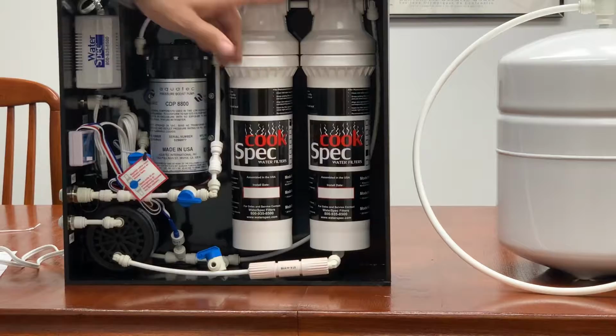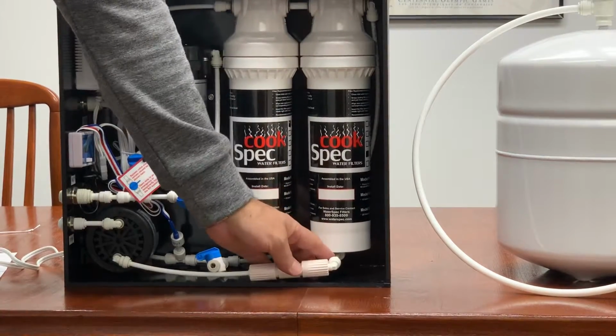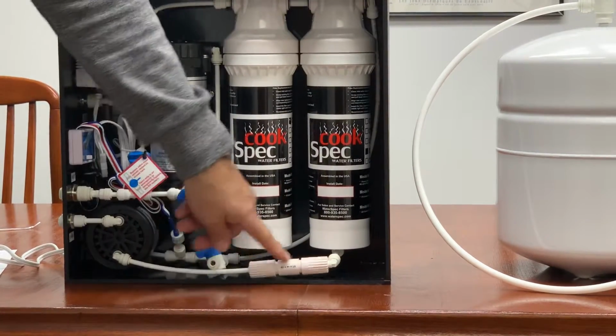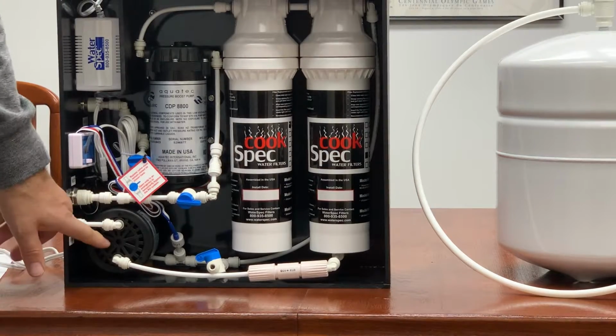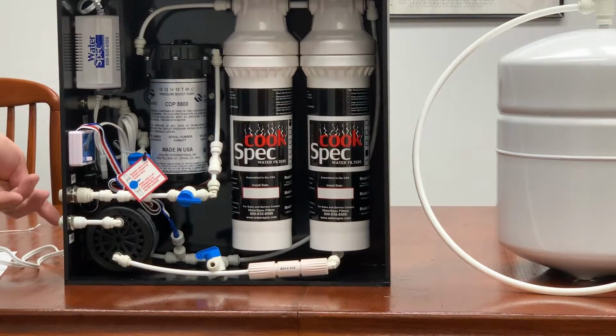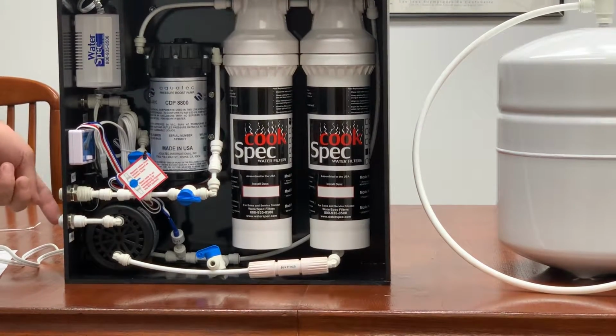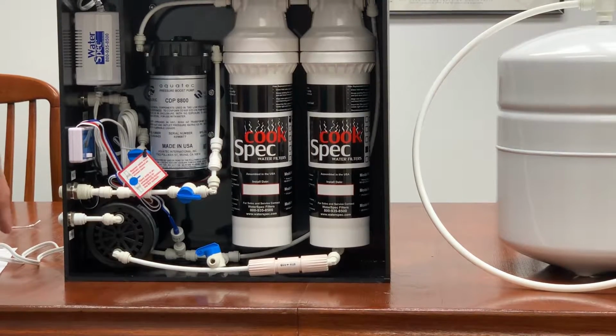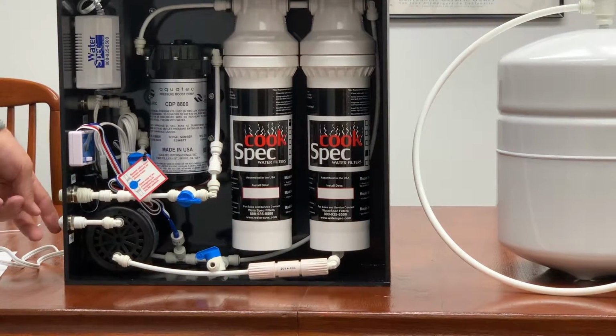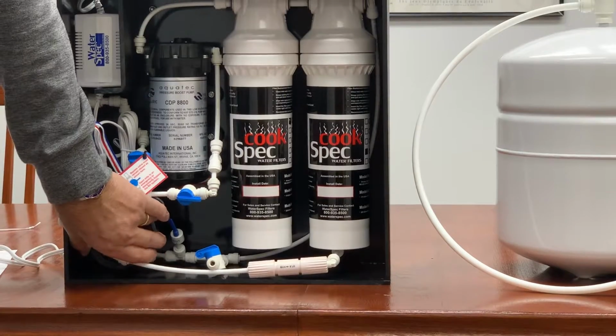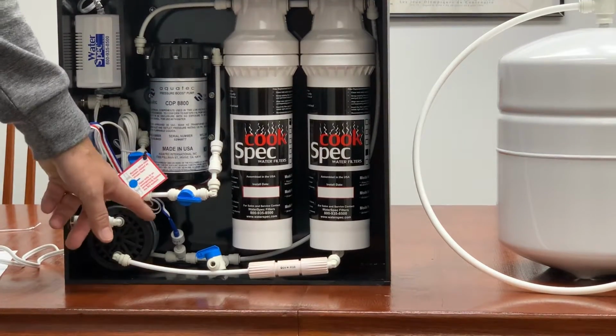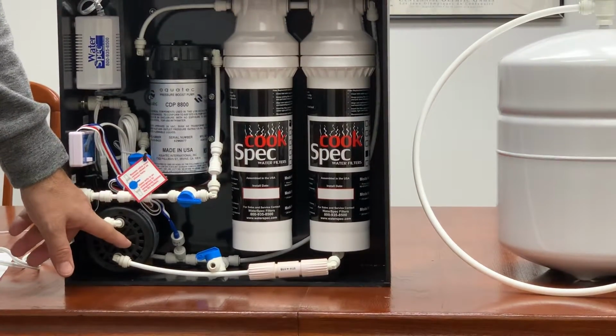On the drain side, which is the bottom part of the membrane, you have a drain flow controller. It goes to the bottom of the permeate pump, and then you have a 1/4 inch line which goes out to an open drain with an air gap in it. The permeate pump is a water saving device, but it also acts as an automatic shut-off valve.